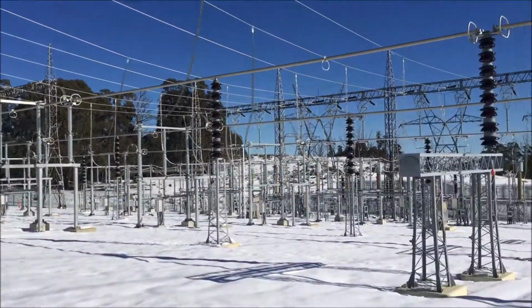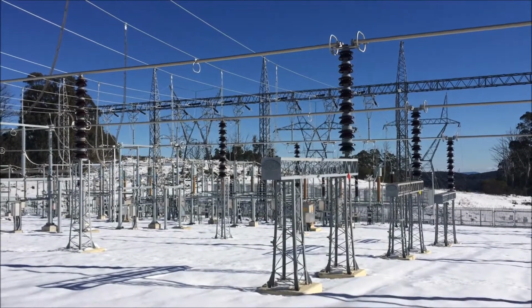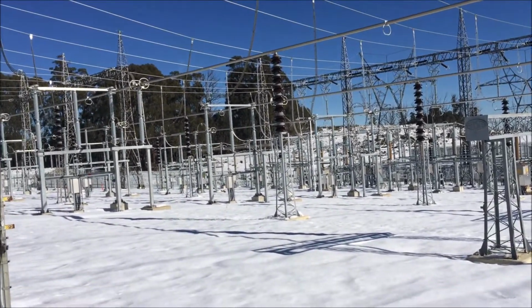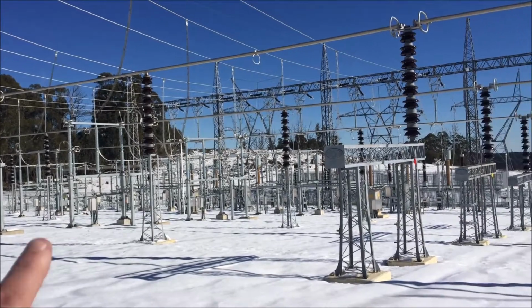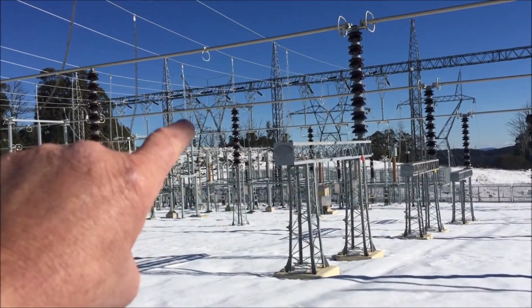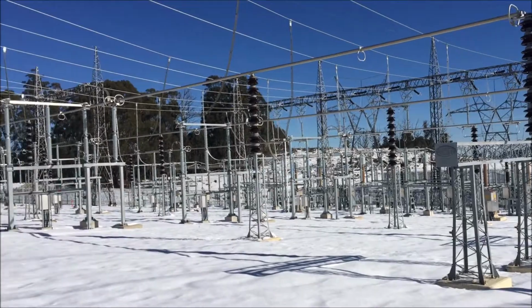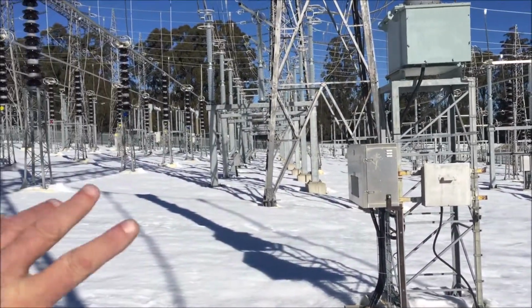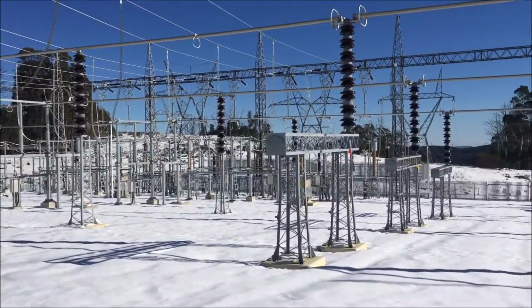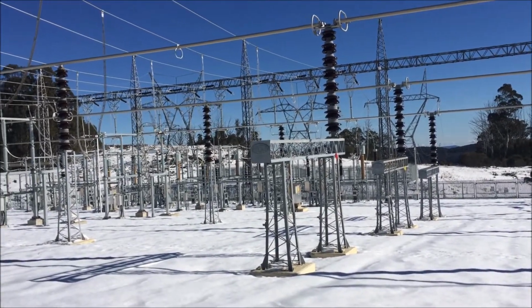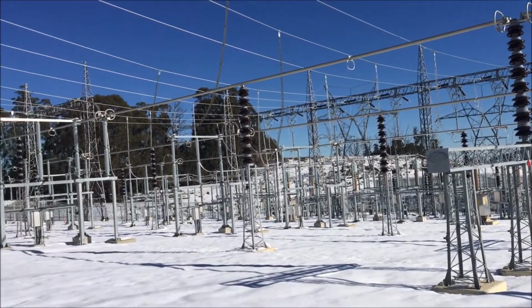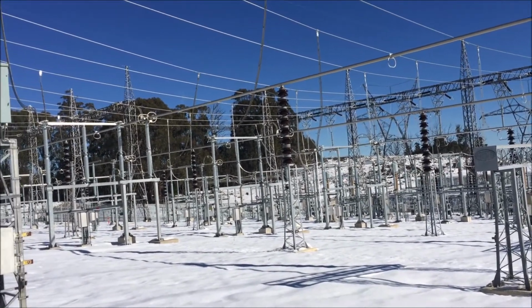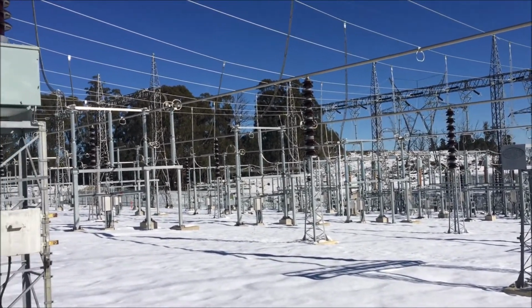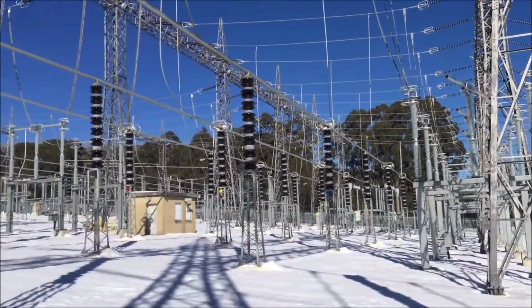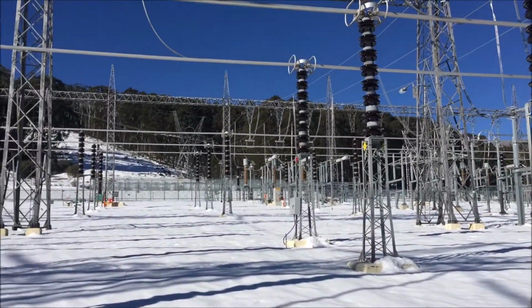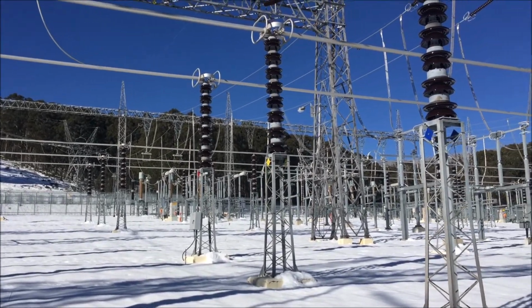It's sort of a good idea, but when it comes to bus bar protection, it becomes a nightmare because each feeder, each line, there's CT contributions come out, and they used to go to a summation kiosk somewhere, but how do you change that over when you're swapping the line onto the reserve bus? They used to have, I think it was in the actual isolator boxes, they'd switch the CT secondaries in there, which just fills me with dread, and apparently it used to worry a lot of people.